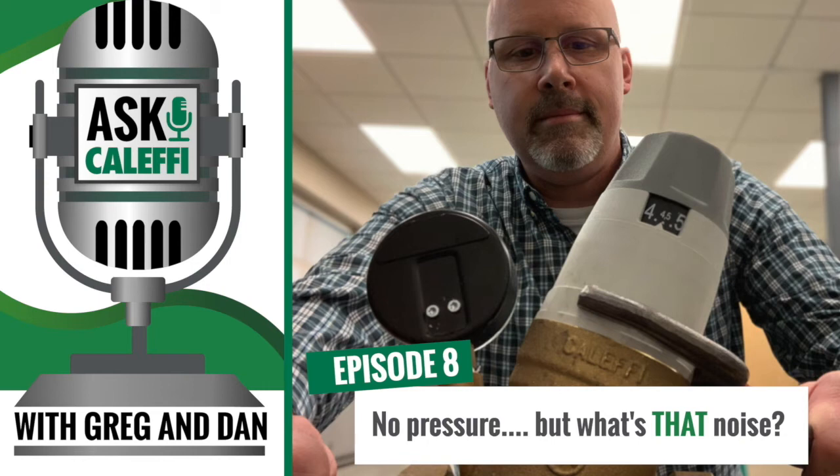It'd be important to do that — total up what you think your shower flow rates are, lavs, dishwasher, washing machine, and come up with a total GPM. When you look at sizing, that's what's really important. What you did is pretty common — you sized it based on pipe size coming in and through the home. Our valves are pretty high flow, so it's not uncommon to see a pressure reducing valve that's one or even two pipe diameters smaller than the incoming piping.